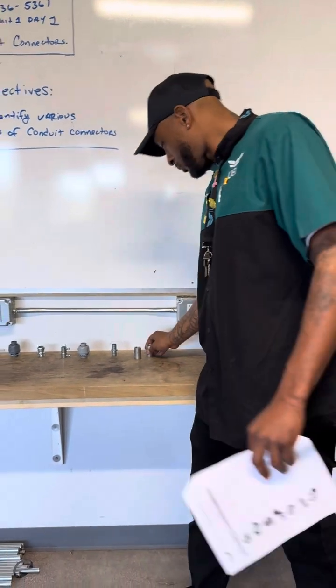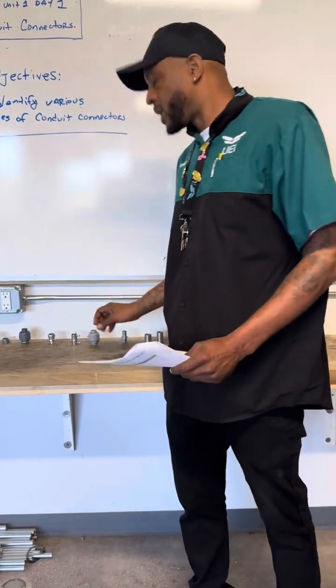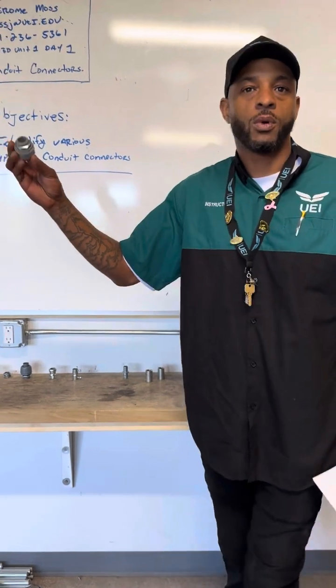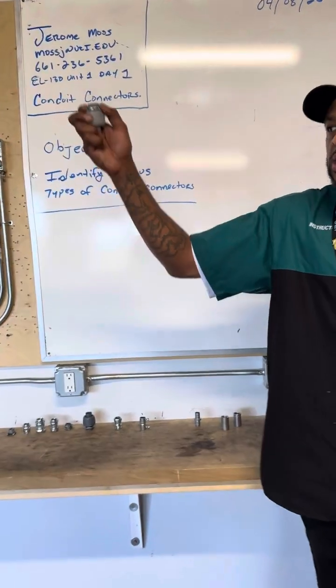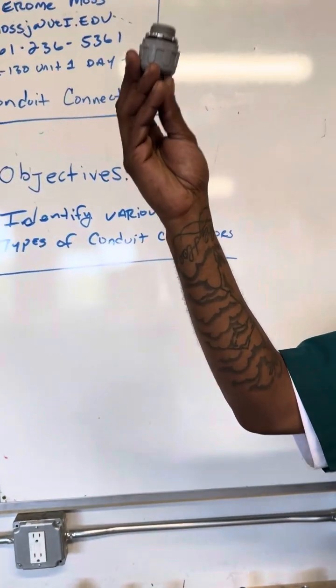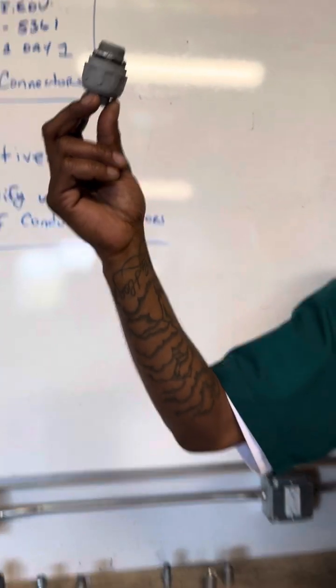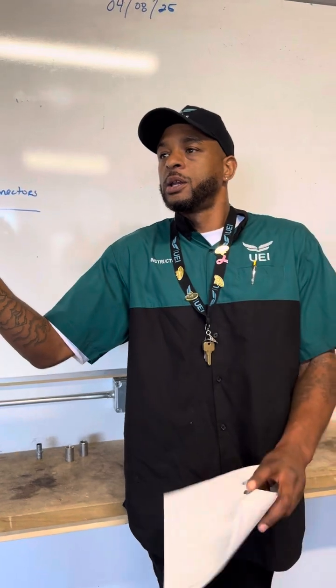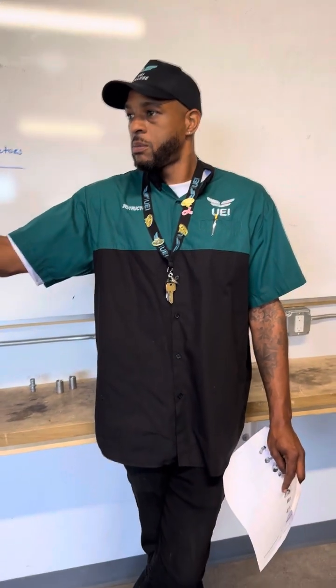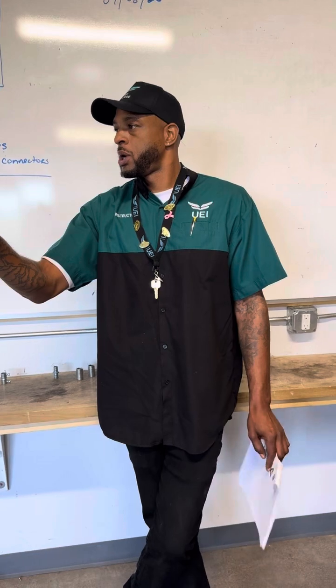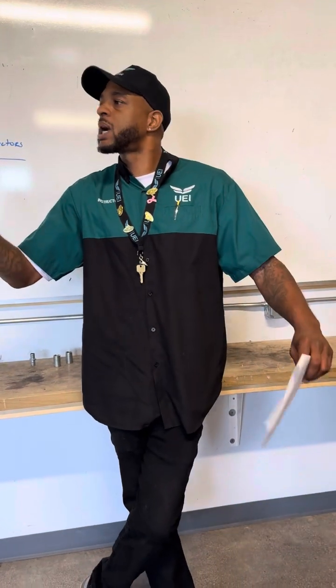Okay. The next one we're gonna go over is, let's skip to number 11. Okay. This is a seal tight, known as a liquid tight connector. Okay. You always know the difference between a connector or coupling depending on the lock ring at the top. Anything that inserts is some form of a connector. Anything that extends the pipe is a coupling.